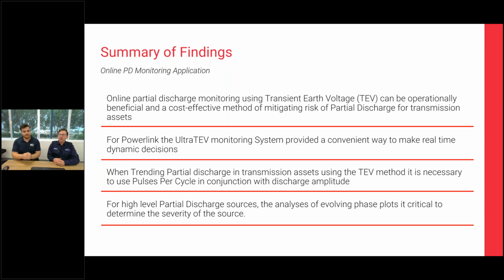From a pure data analysis point of view, it was quite interesting, rather than focusing on the pure amplitude of the TEV and what we were seeing, to start to trend the pulses per cycle. We really focused on the pulses per cycle along with the phase plot analysis.